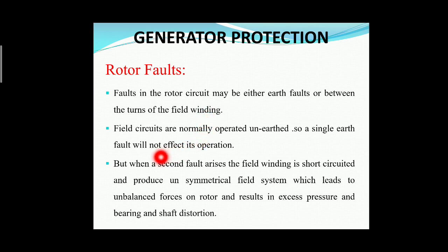The field circuits are normally operated unearthed. In the case of the rotor, the field circuit is operated unearthed, so a single earth fault will not affect its operation. But when a second fault arises in the field winding, that part is short circuited and produces an unsymmetrical field system, which leads to unbalanced forces.